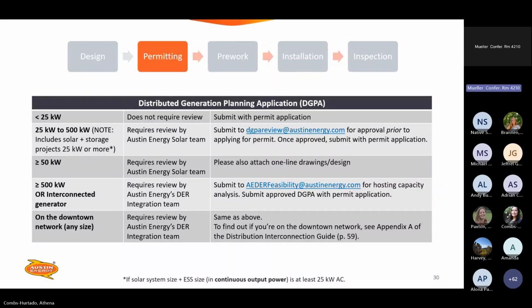So the DGPA, these are different size systems here and how to interact with our system based on what size system you're installing. If it's less than 25 kW total, it does not require a review. You can submit with a permit application. If your system is between 25 and 500, this is including solar and storage, this will require review by the Austin Energy Solar Team. So please use that email address there, dgpa-review@austinenergy.com, for approval prior to applying for permit, because you will want to include that approved DGPA on your permit.